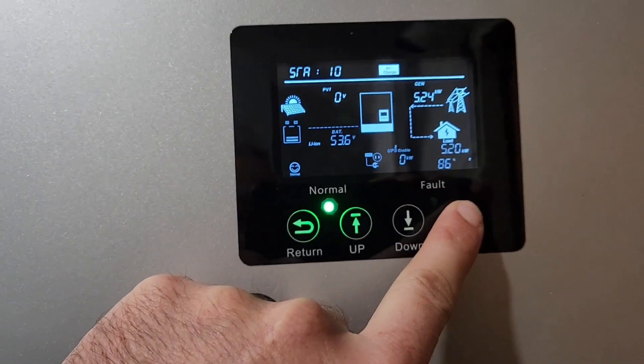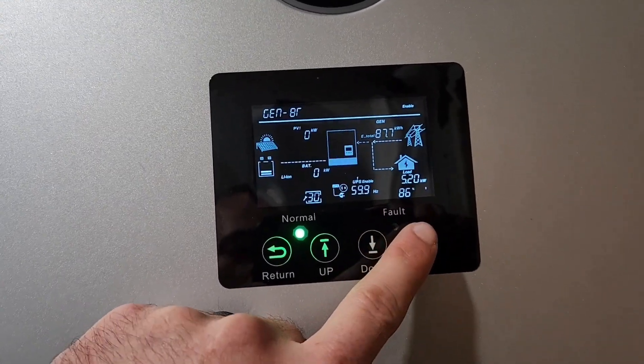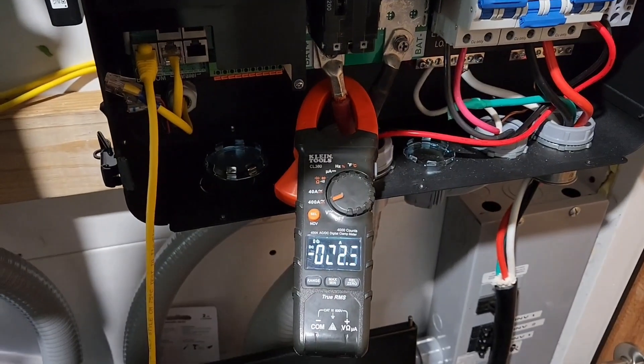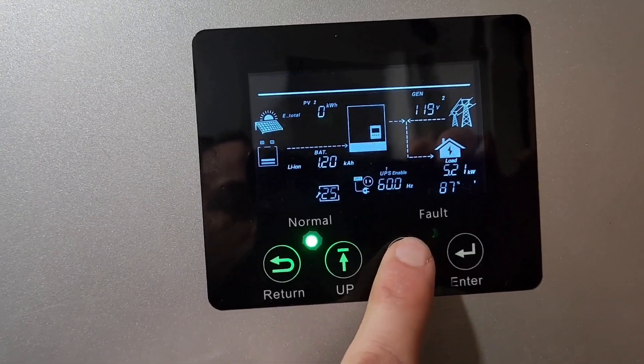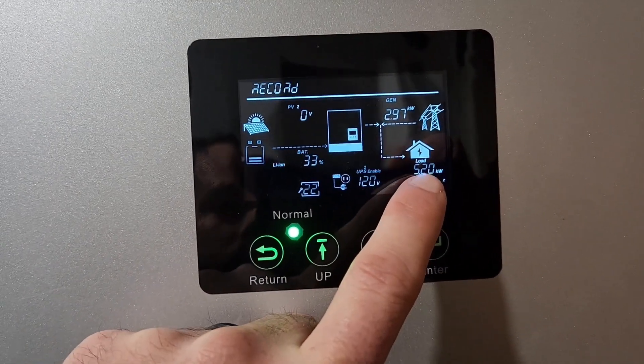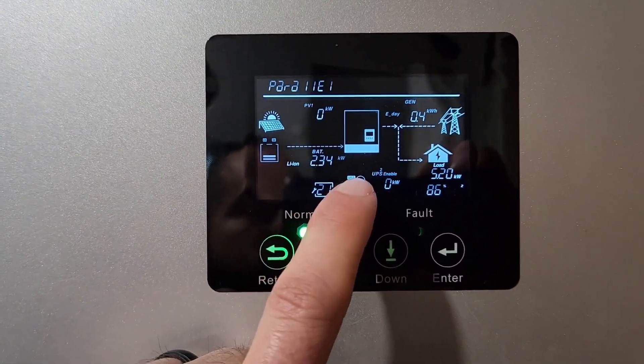Let's go ahead and turn that feature back on. I'm going to hit Enable. And look at that — it jumps straight up. So now we're pulling 3 kilowatts from the generator, we're supplying a 5 kilowatt load, and the batteries are supplying 2.3 kilowatts.